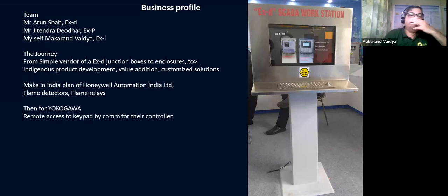Then for Yokogawa, we both worked on a challenge with the controller. For example, this is a controller. In a hazardous area, you cannot just touch a controller to set the temperature or change its parameters, because you cannot open the door. Opening the door requires loosening a lot of Allen bolts, and that's not possible or recommended in a running plant. So there's no question of opening that door except for maintenance. Even a simple set point change is not possible. So how to do that?